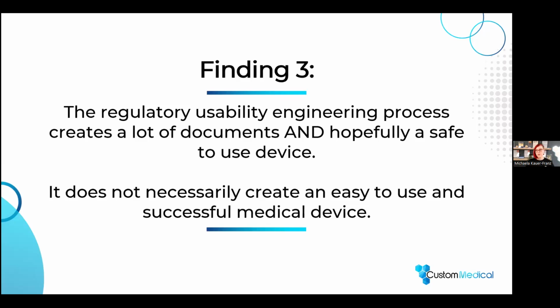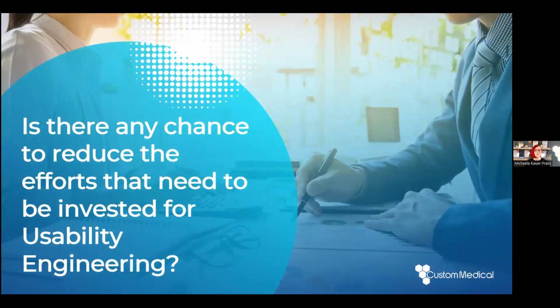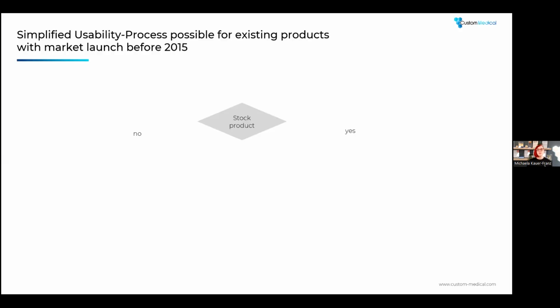I know that this sounds like quite a lot of stuff to do, and it can be. So I guess some of you are asking if there's any chance to reduce the efforts that are needed to be invested for usability engineering. And yes, there is a chance to reduce it. I brought for you the simplified usability engineering process, which is possible to apply for existing products with a market launch before 2015. So for stock products, basically.